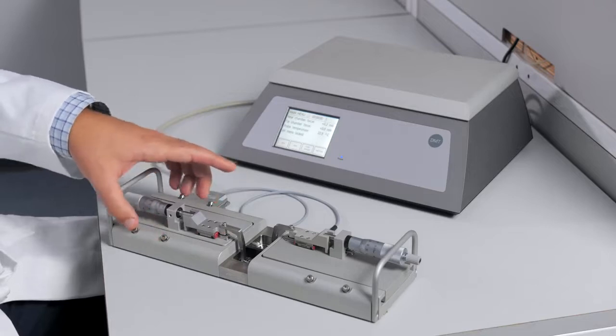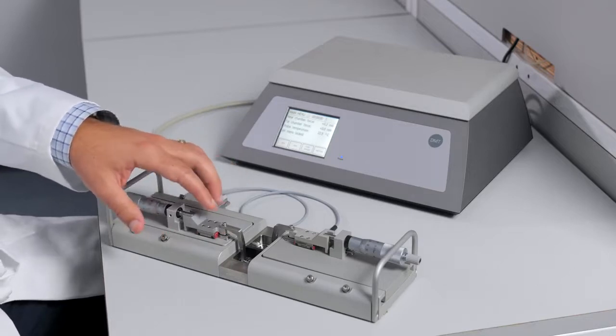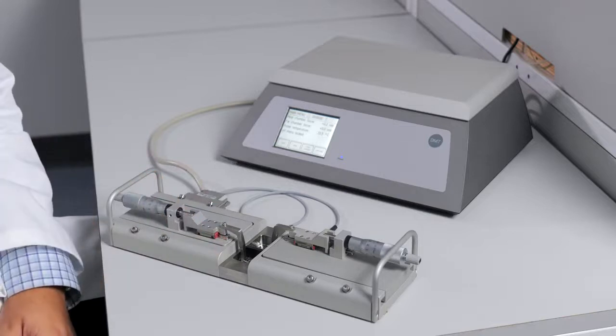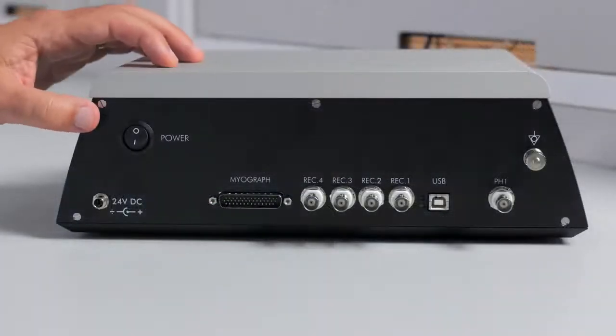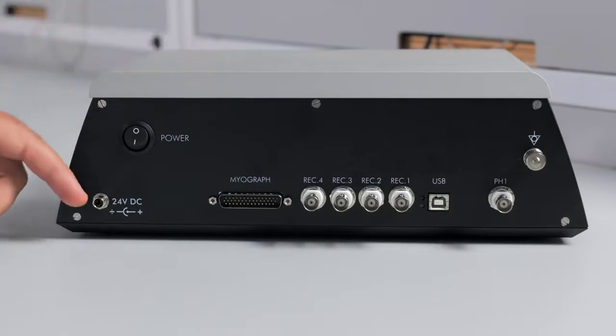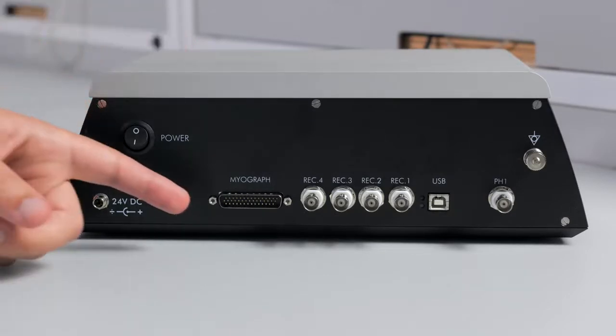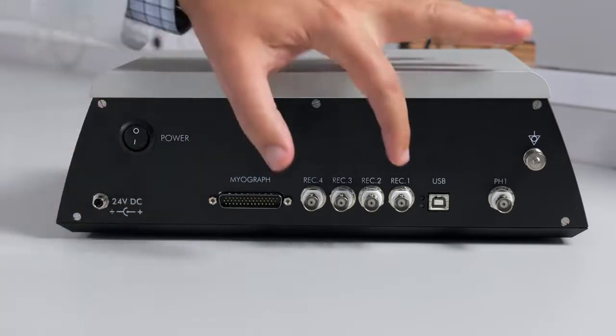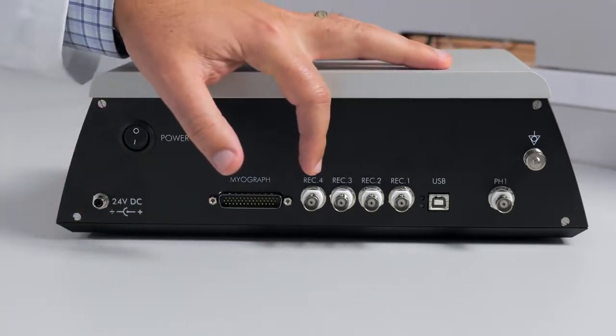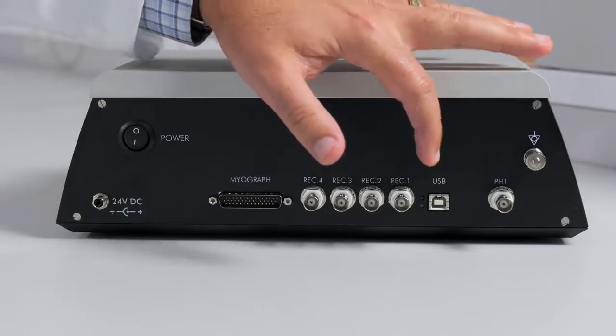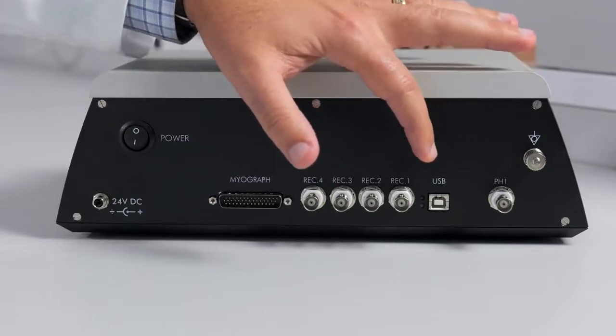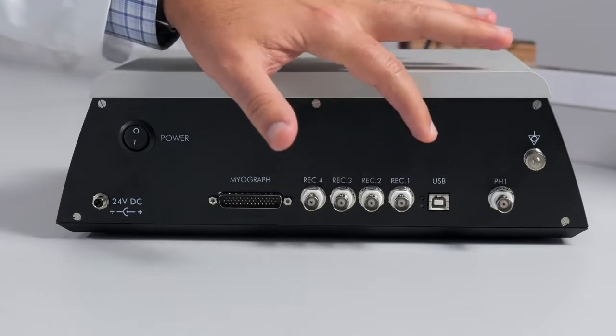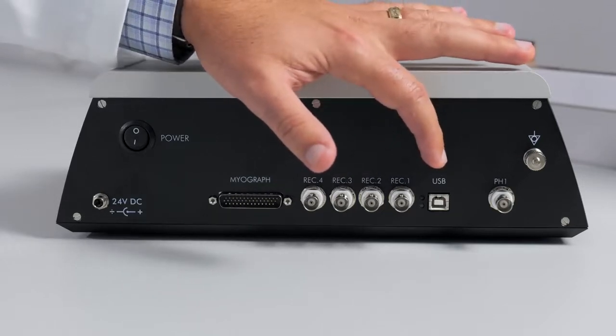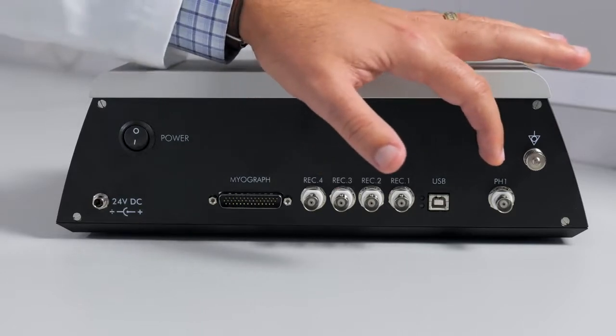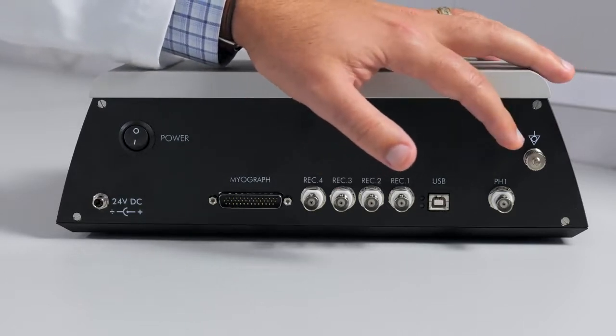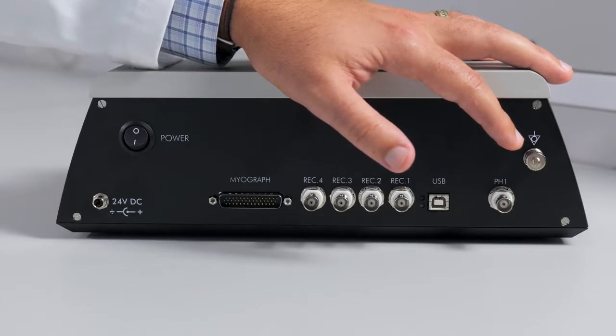Each side also has 4 positioning screws that allows you to accurately align the two jaw mounts. The back of the interface has all the connections to fully utilize the system. You have a power supply and a power switch. You have a connection for the myograph cable, 4 BNC outputs to collect the raw data from the myograph. You also have a USB connection, which will allow you to bypass the BNCs in the analog to digital converter and go straight to your data acquisition. This is the connection for the optional pH probe. And lastly, there is a ground connection to eliminate any electrical noise.